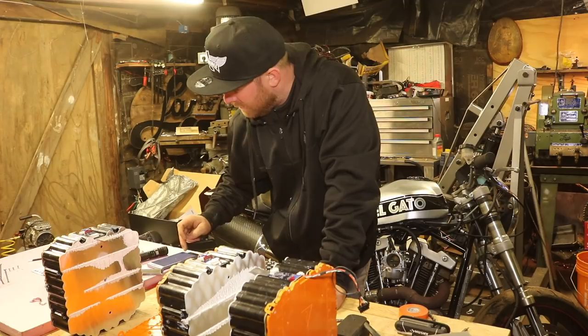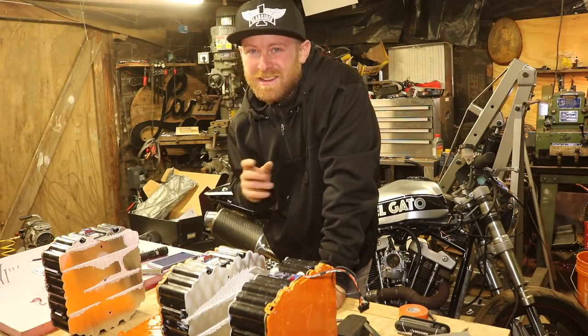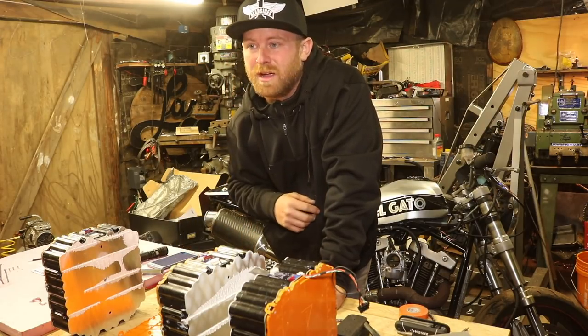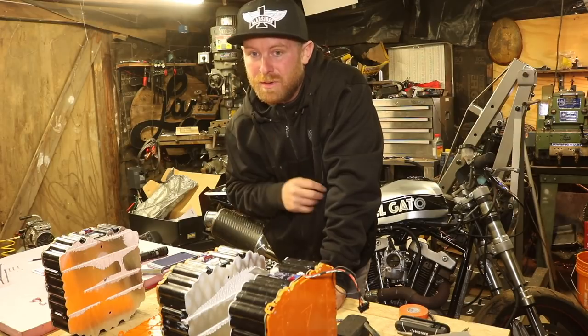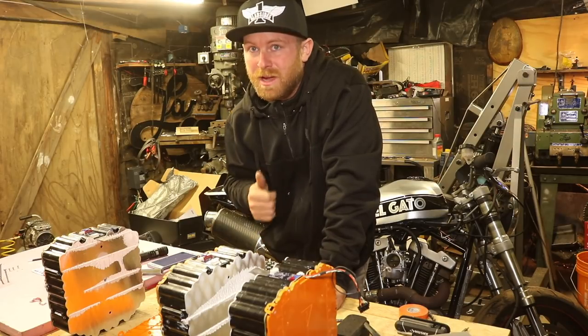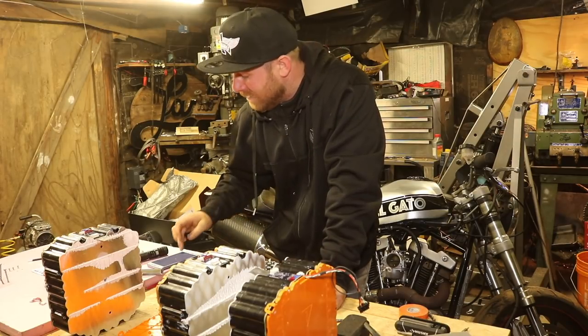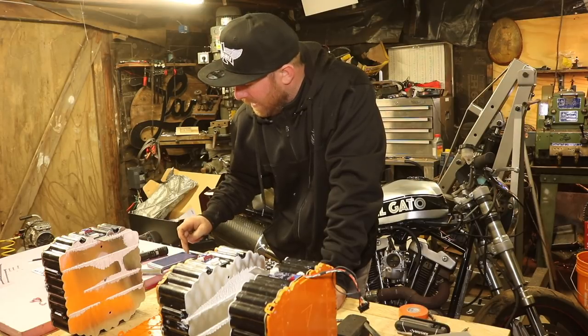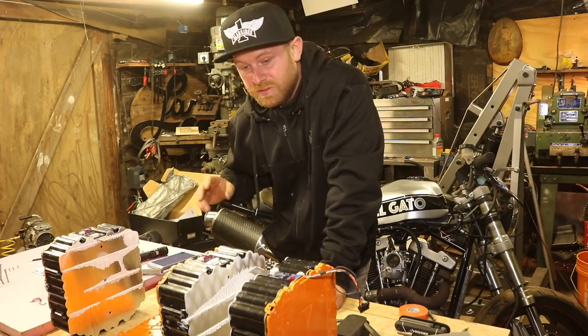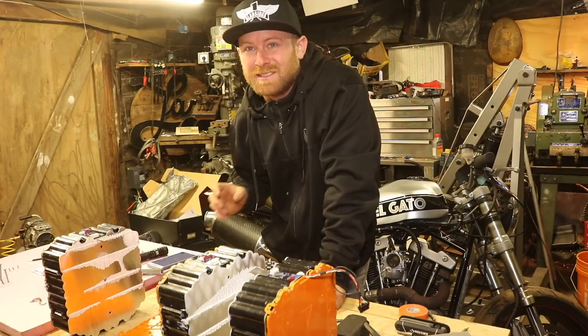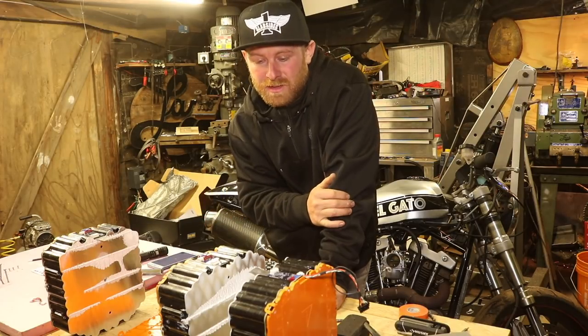3.6 times 80 gives me 288 nominal volts. That's way too low - my operating system, I think nominal minimum is 320, and I want to be upwards of 380 if I can. Even the max cell voltage at 4.2 charging on these is 336 max volts, so that's too low.